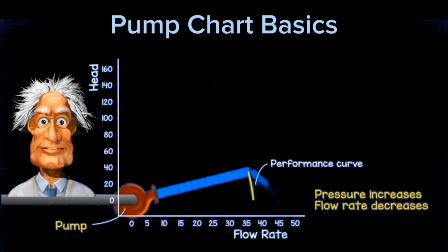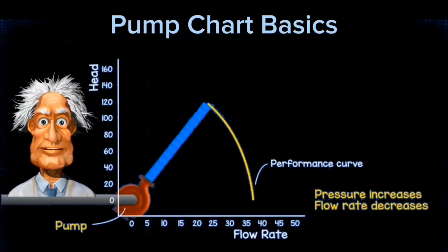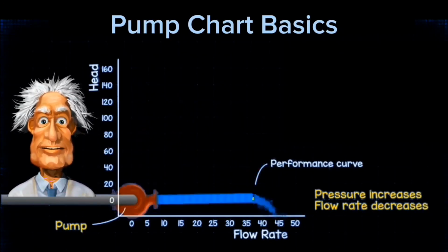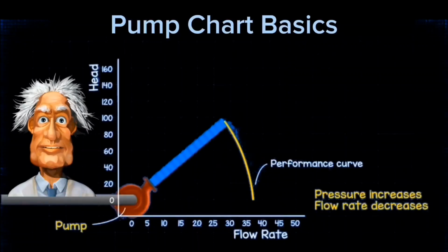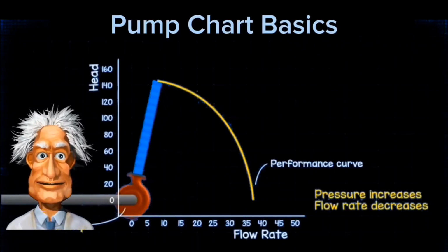By recording the values during this elevation, we basically get our performance curve, although we will note that pump manufacturers don't test pumps this way as it's not practical.